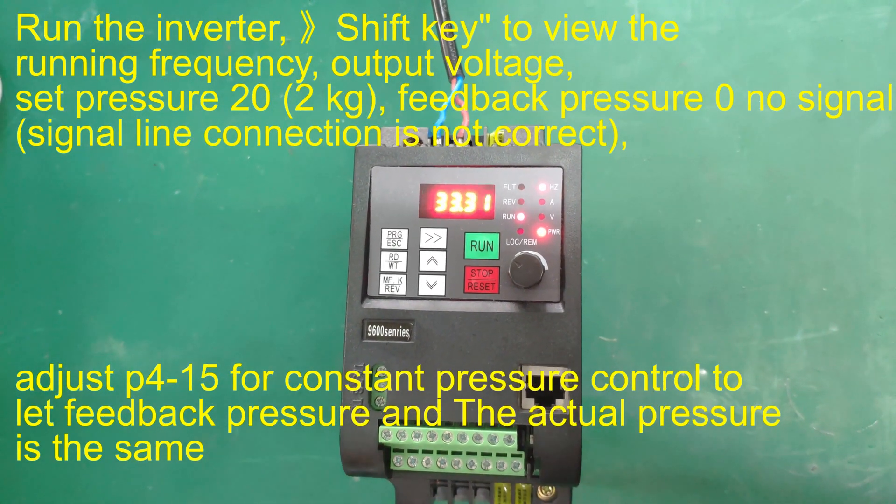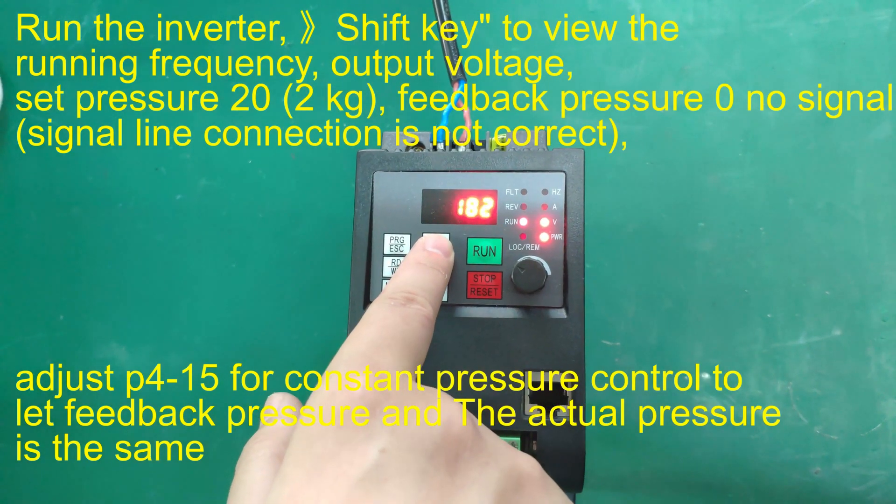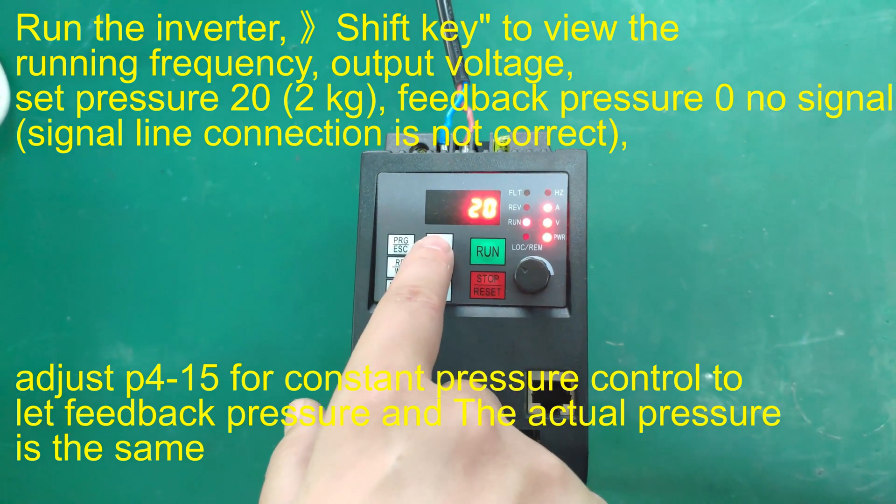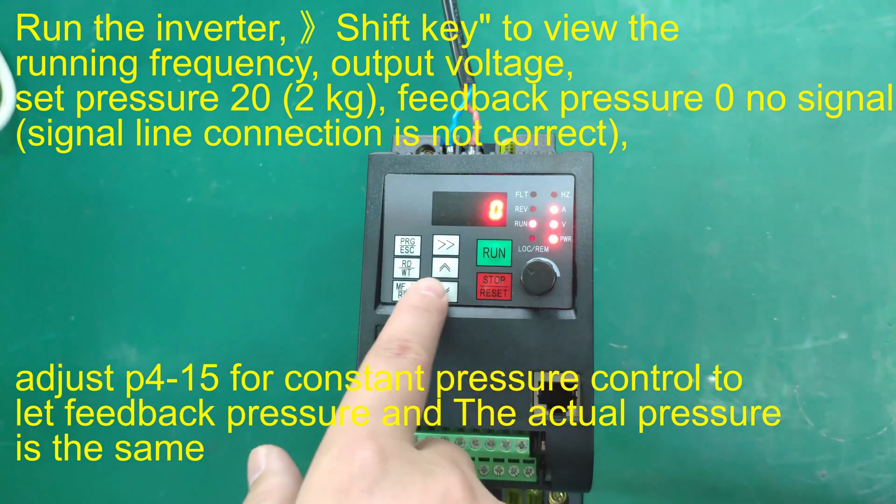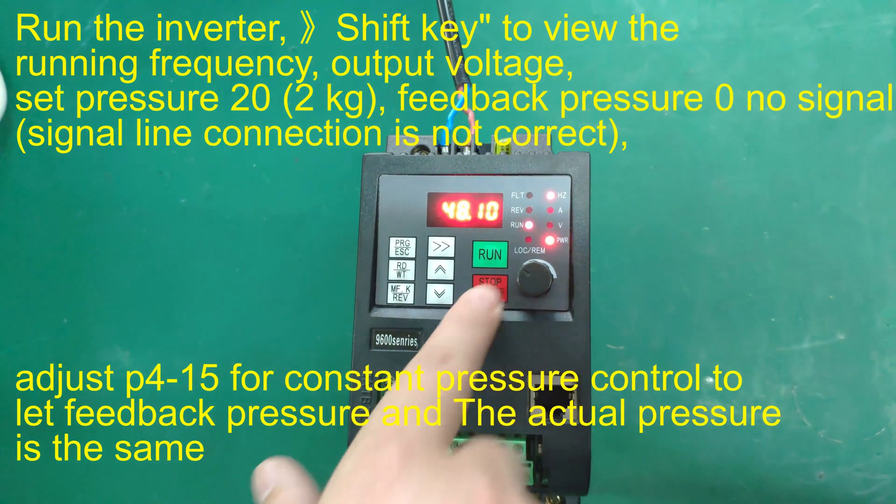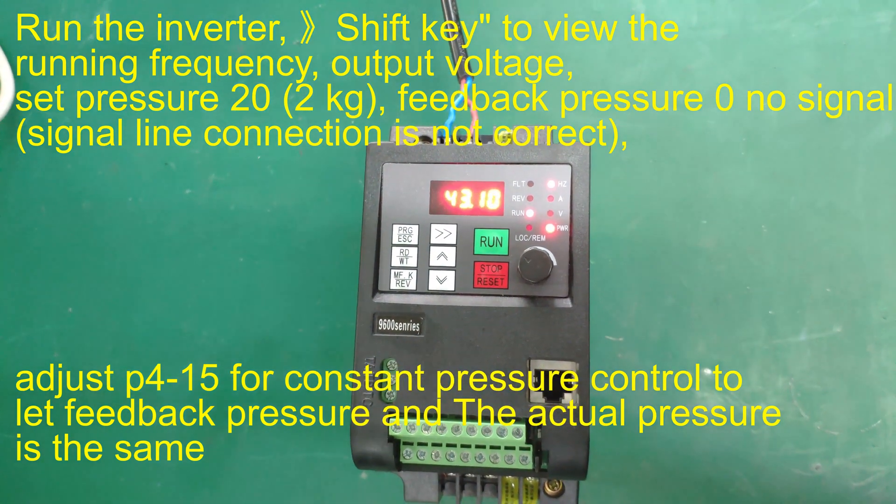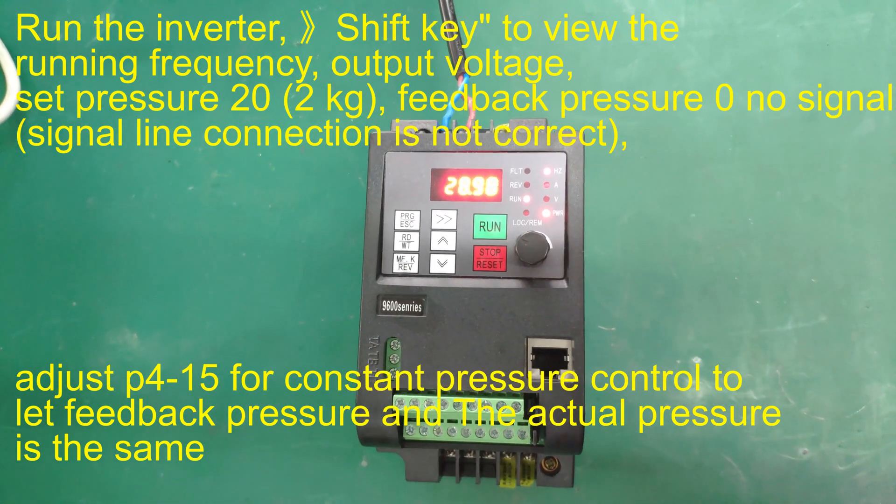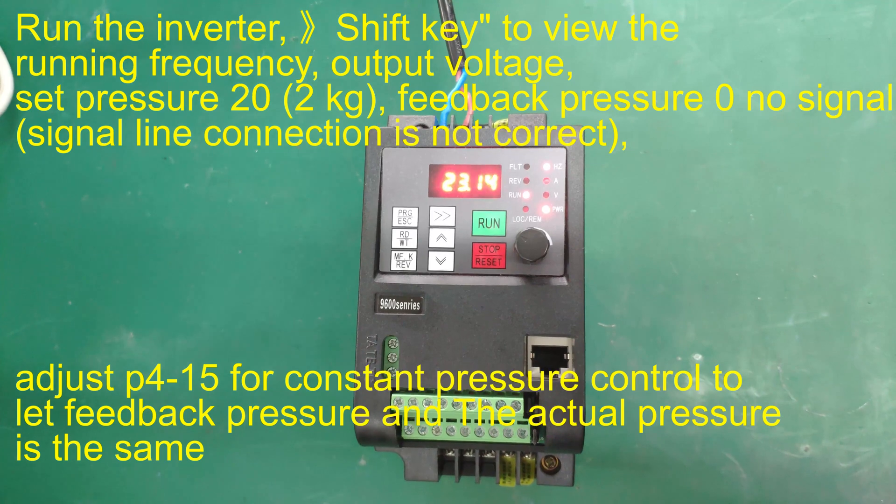Run the inverter, shift key to view the running frequency, output voltage, set pressure 20 (2kg), feedback pressure 0 no signal (signal line connection is not correct). Adjust P4-15 for constant pressure control to let feedback pressure and the actual pressure be the same.